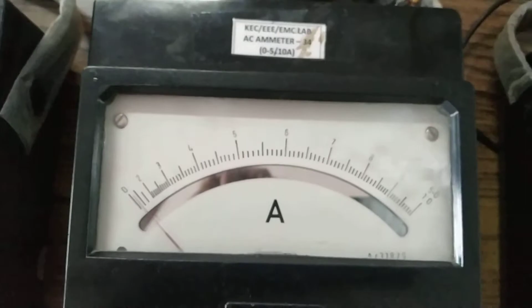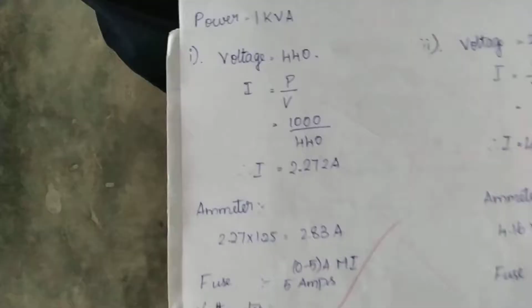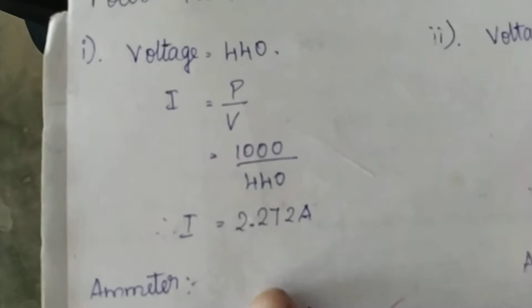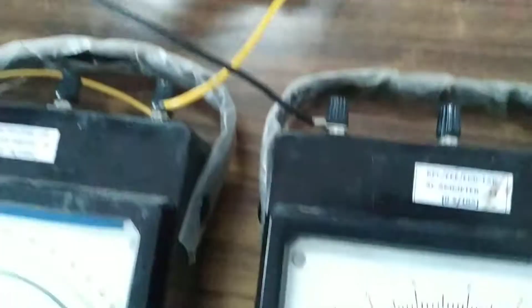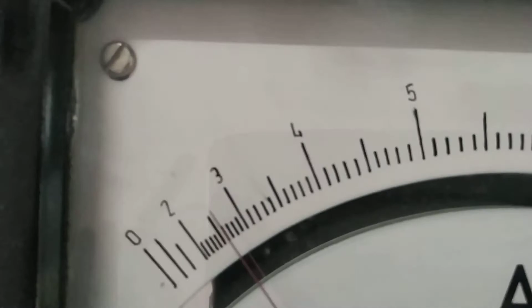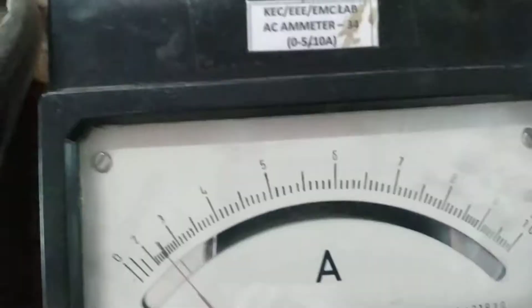Now we are going to give power to the transformer with respect to the ammeter value. The primary current value we need to apply is what we calculated as 2.272 ampere. So with the help of the auto transformer we need to apply 2.27 by varying it. Our scale will be in 10 ampere, am I right? If you look at the scale, it is in 10 ampere.